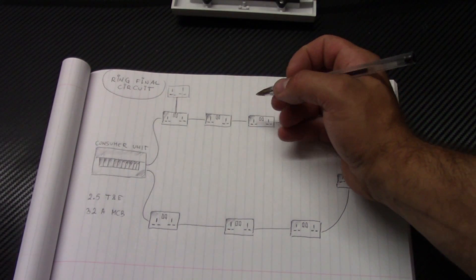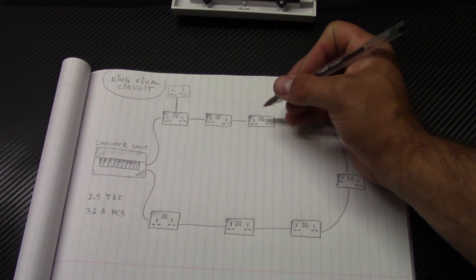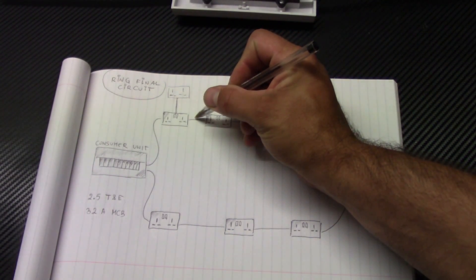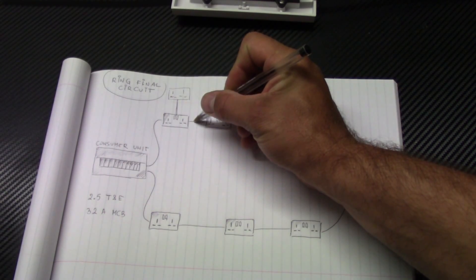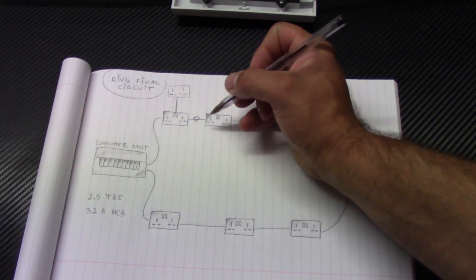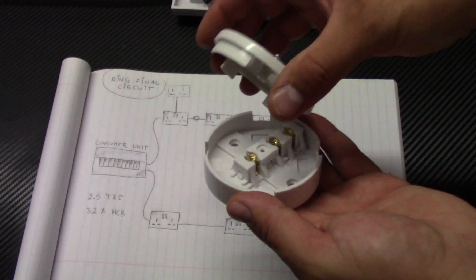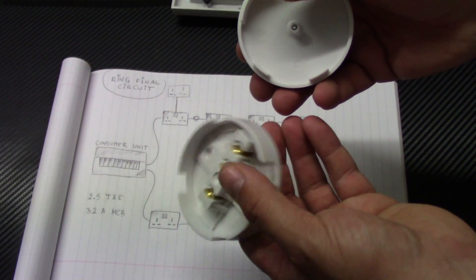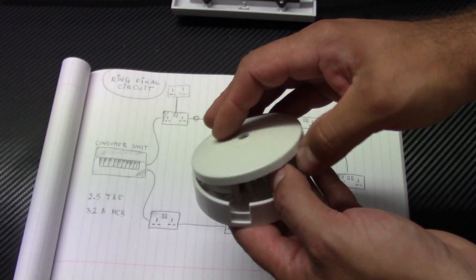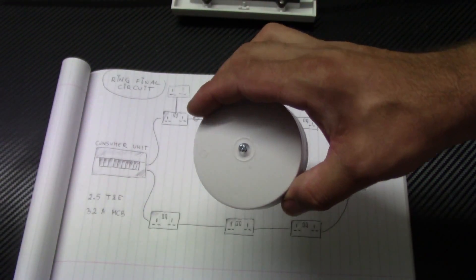There is also another way of making a spare from the ring circuit. We can make a junction box in between two sockets on a ring. The junction box has to be 30A with three terminals. I'll show you in a minute how to fix it.